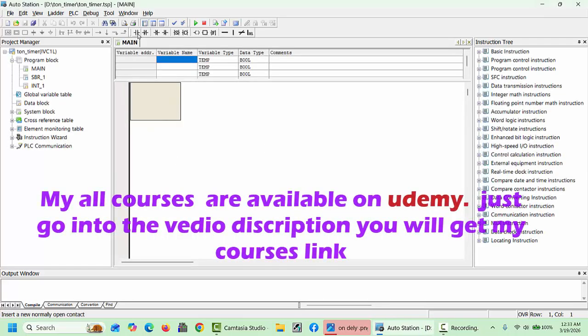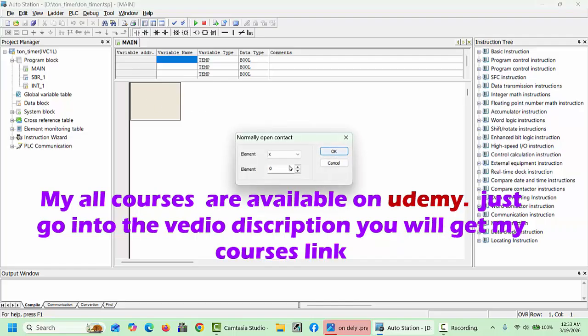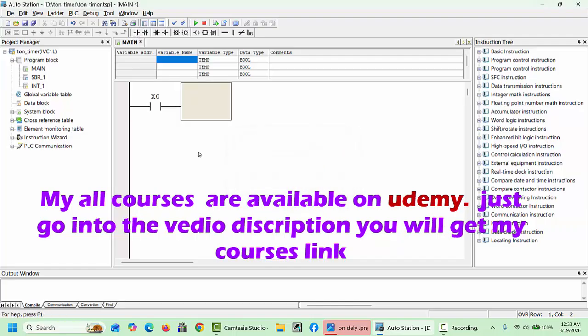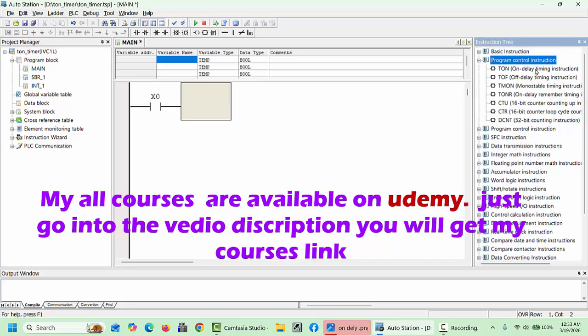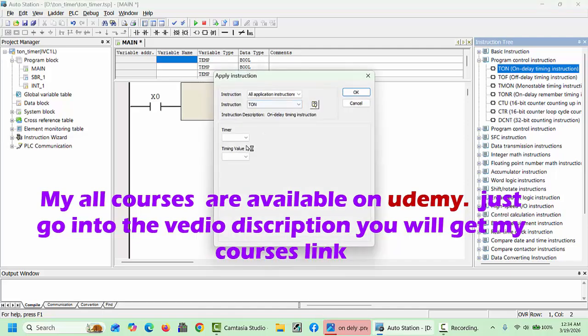Next we have to choose one open contact of our PLC, X0 for example. And next we will take the timer from the program control instructions. Click on this icon and the first command you can see is TON, the on delay timing instruction. You can drag and drop this function into the ladder chart, and after that you have to give the address.